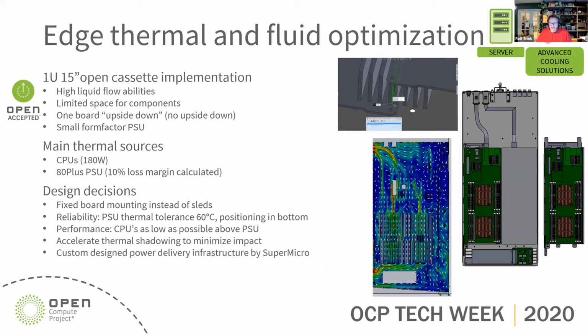I've included some examples of how we've dealt with that, because if we're looking at a 15-inch chassis, it's not actually possible to fit the two specific boards we need side by side on the same baseplate. So one of the boards is oriented upside down. Now, with immersion, chassis aren't positioned horizontally anymore - we're talking about vertical implementation, which means there's no such thing as upside down, they're all straight up. So you have some additional design liberties when solving these types of challenges.